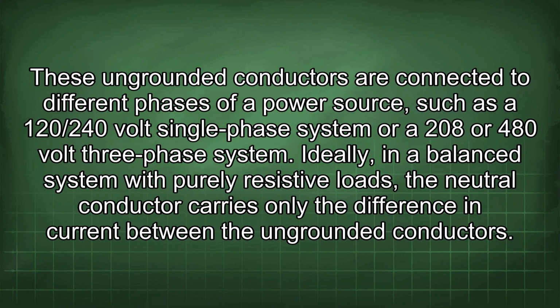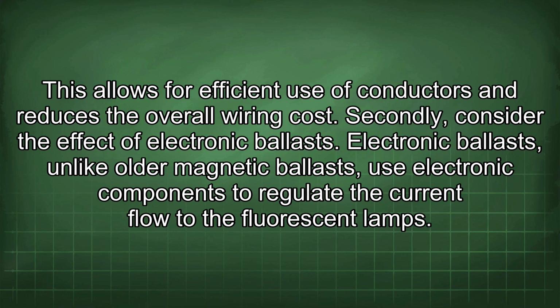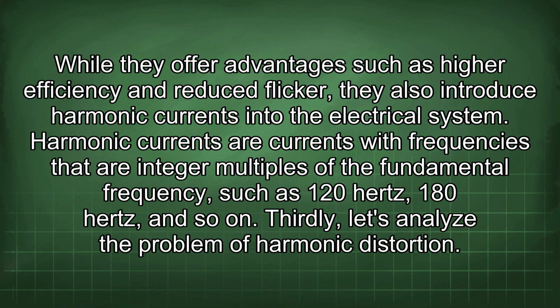Ideally, in a balanced system with purely resistive loads, the neutral conductor carries only the difference in current between the ungrounded conductors. This allows for efficient use of conductors and reduces the overall wiring cost. Secondly, consider the effect of electronic ballasts. Electronic ballasts, unlike older magnetic ballasts, use electronic components to regulate the current flow to the fluorescent lamps. While they offer advantages such as higher efficiency and reduced flicker, they also introduce harmonic currents into the electrical system. Harmonic currents are currents with frequencies that are integer multiples of the fundamental frequency, such as 120 Hz, 180 Hz, and so on. Thirdly, let's analyze the problem of harmonic distortion.